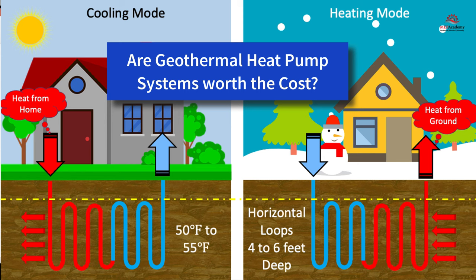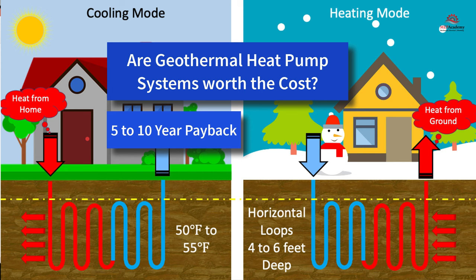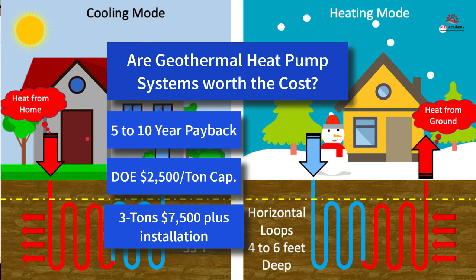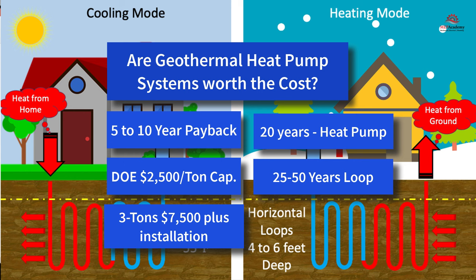Is a geothermal heat pump system worth the cost? Energy savings from the installation of a geothermal heat pump system could take anywhere from 5 to 10 years to pay back the additional investment costs above a conventional system, according to the Department of Energy. The DOE states that an average geothermal heat pump system costs about $2,500 per ton of capacity — so a 3-ton unit would cost about $7,500 plus installation and drilling costs. A comparable air source heat pump system with air conditioning would cost about $4,000, but the energy costs could easily equate to the extra costs of installing a geothermal system. Geothermal heat pump systems have an average 20-plus year life expectancy for the heat pump itself and 25 to 50 years for the underground infrastructure.